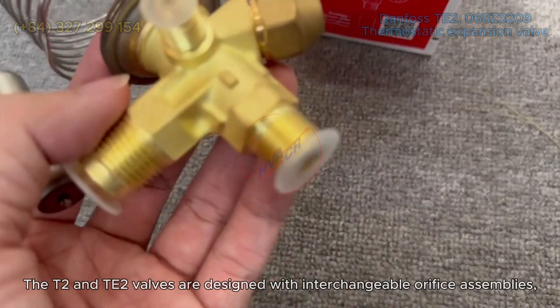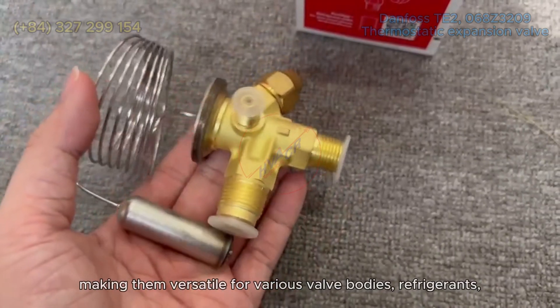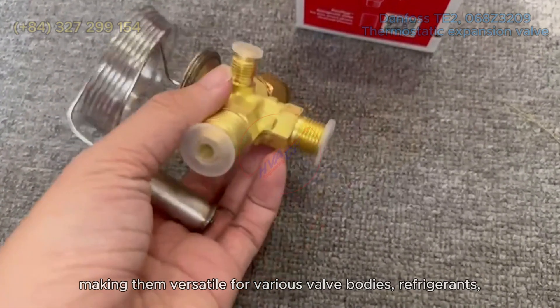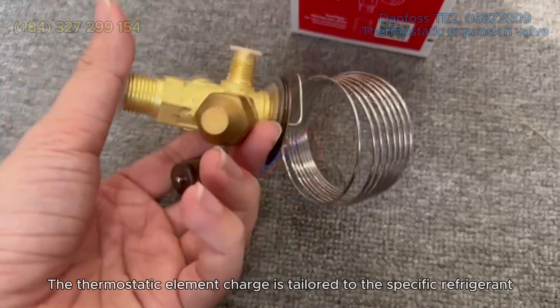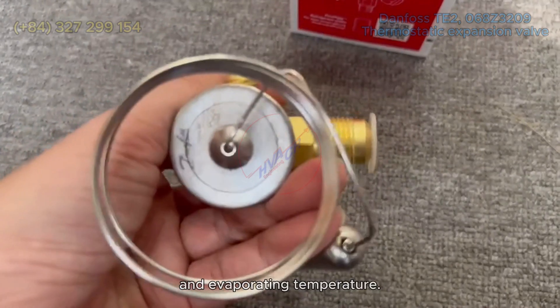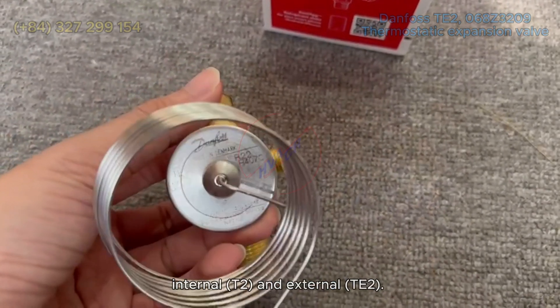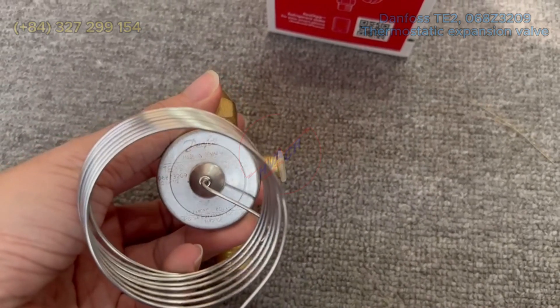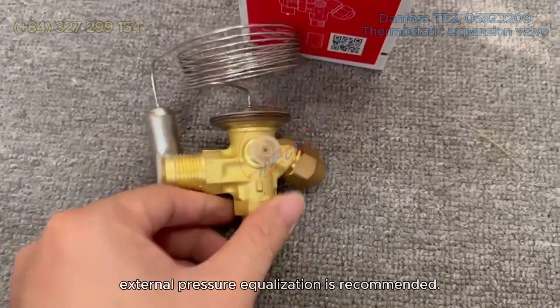The TE2 and TE2E valves are designed with interchangeable orifice assemblies, making them versatile for various valve bodies, refrigerants, and evaporating temperature ranges. The thermostatic element charge is tailored to the specific refrigerant and evaporating temperature. The valves come with two options for pressure equalization: internal (TE2) and external (TE2E). For systems with liquid distributors, external pressure equalization is recommended.